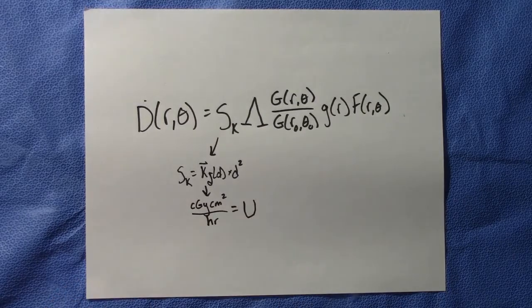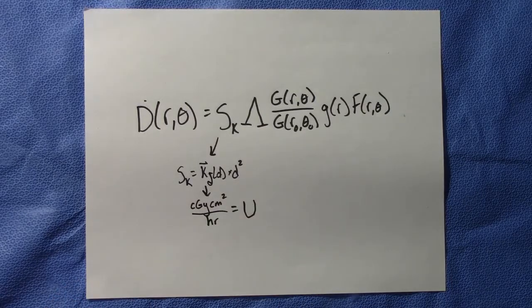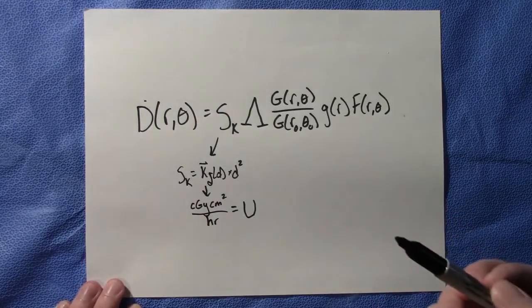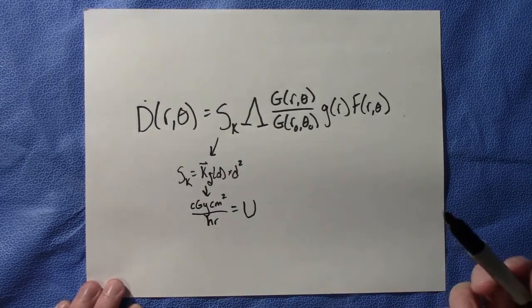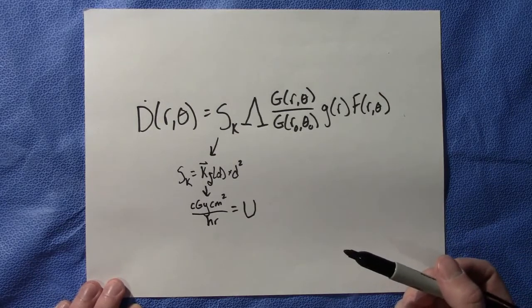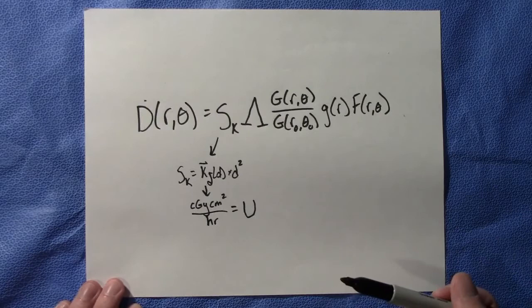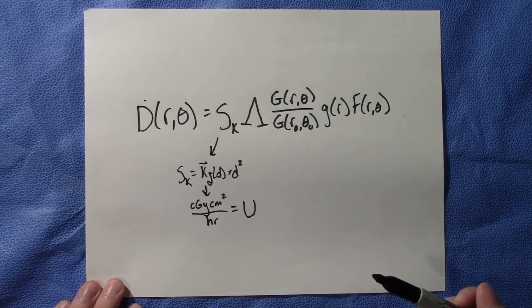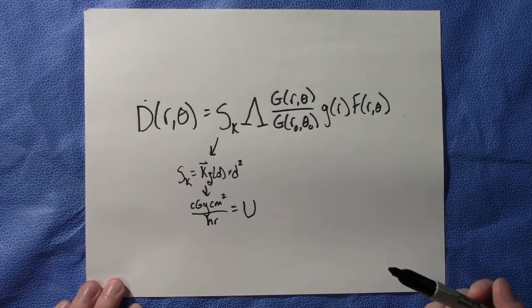Now this air kerma strength is found by NIST using a wide angle free air ionization chamber and you can find that from the manufacturer that you purchase the isotope from.